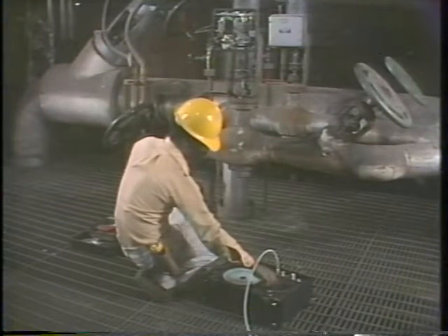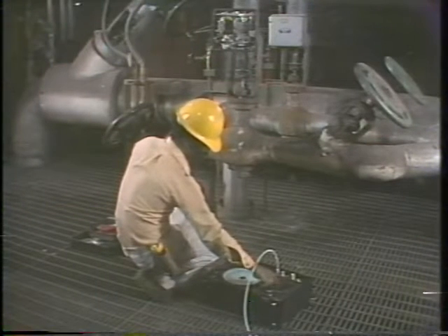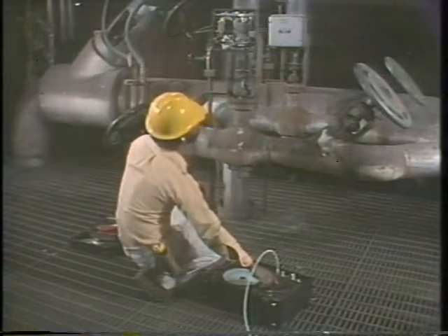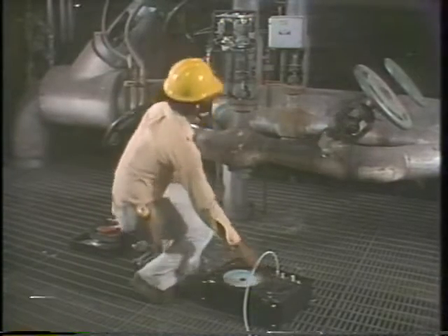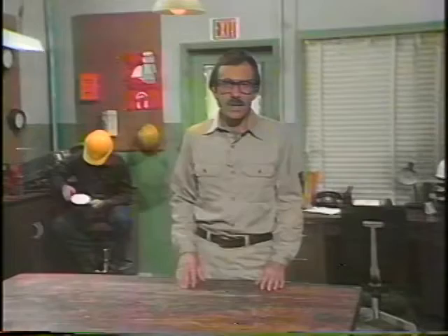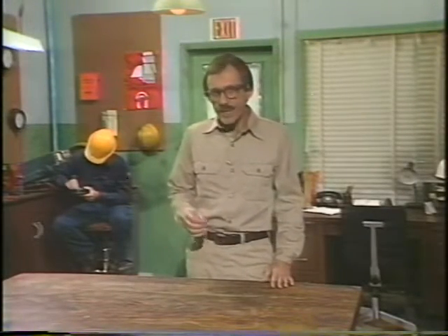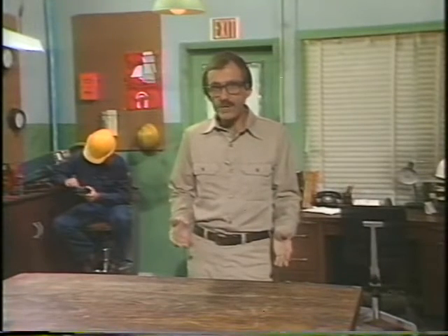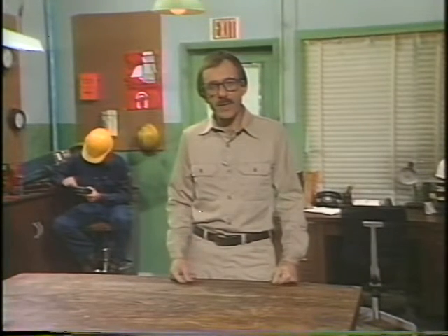Now, this should help you to confirm your diagnosis and locate the most probable cause of the problem. If, when you're testing the instrument, you discover that it has a problem, you'll need to figure out whether the problem is that the instrument is actually damaged in some way or just out of adjustment. Because parts wear and age, causing the instrument settings to change, calibration adjustments can change with time.